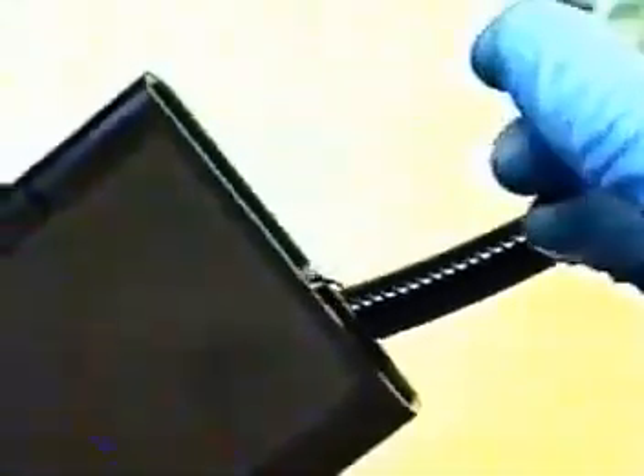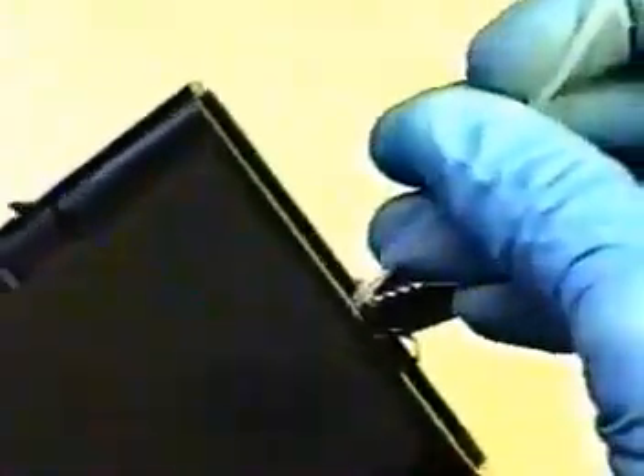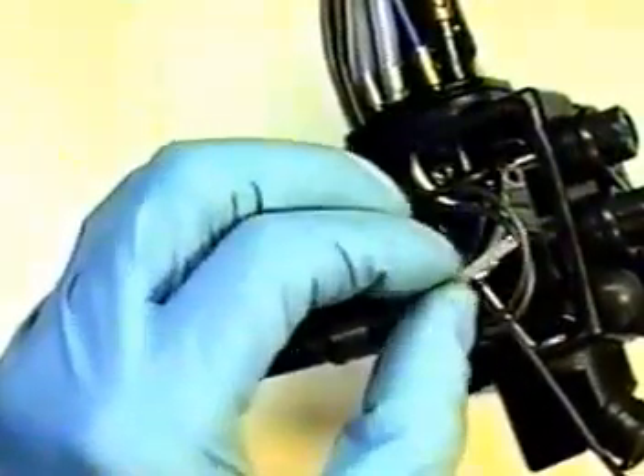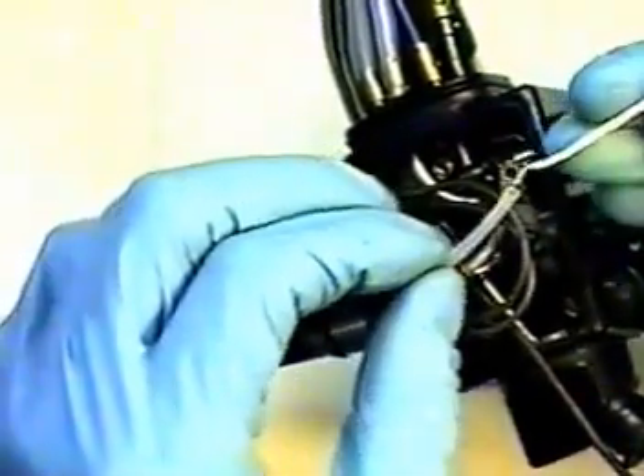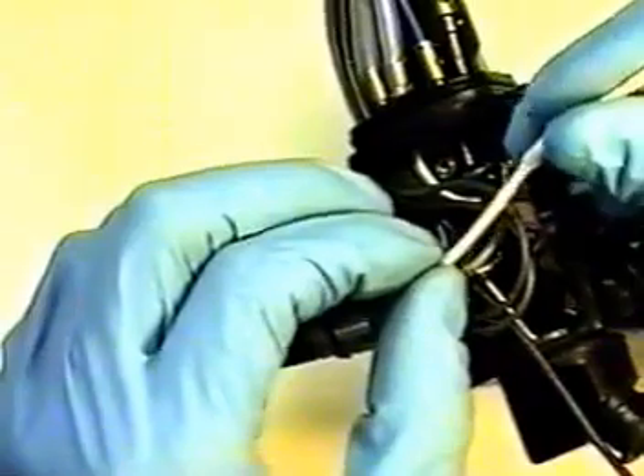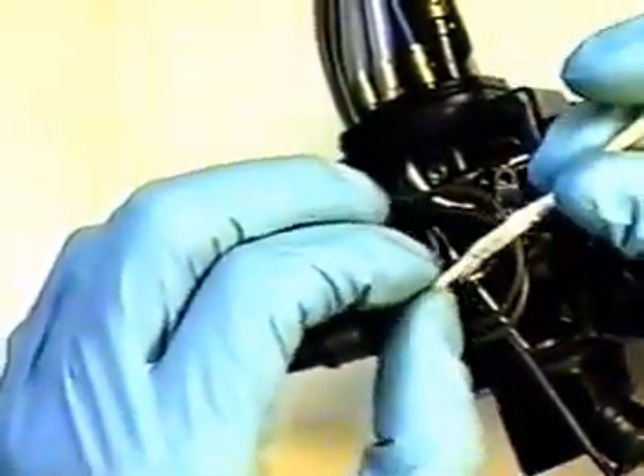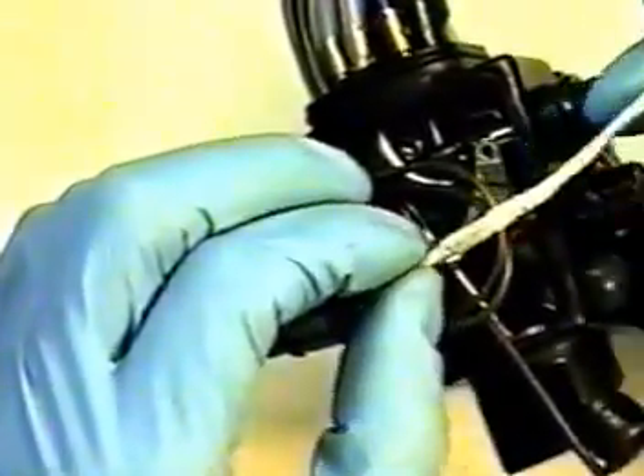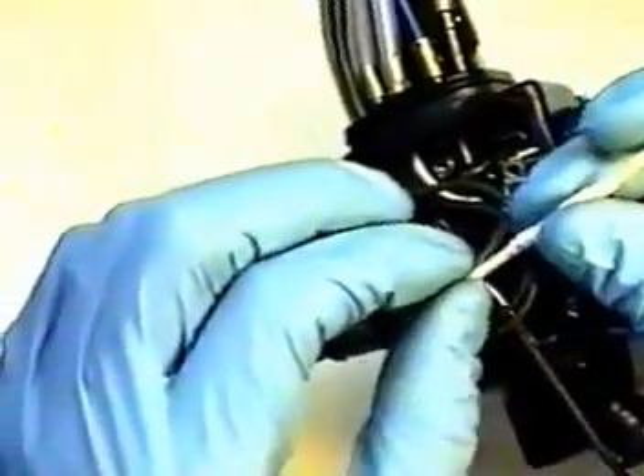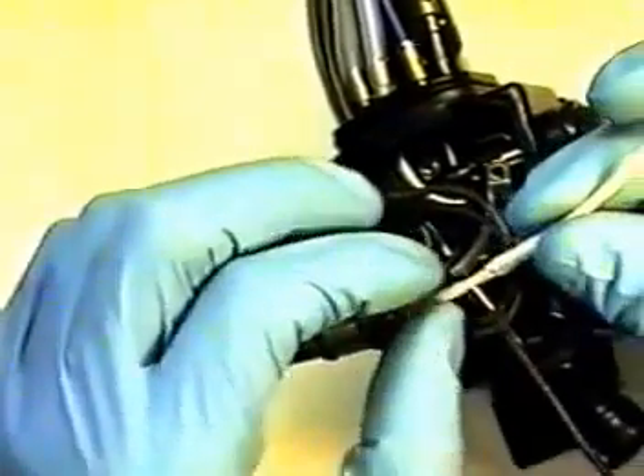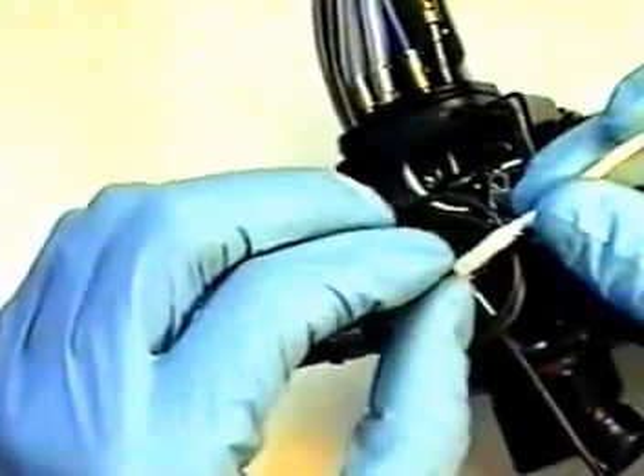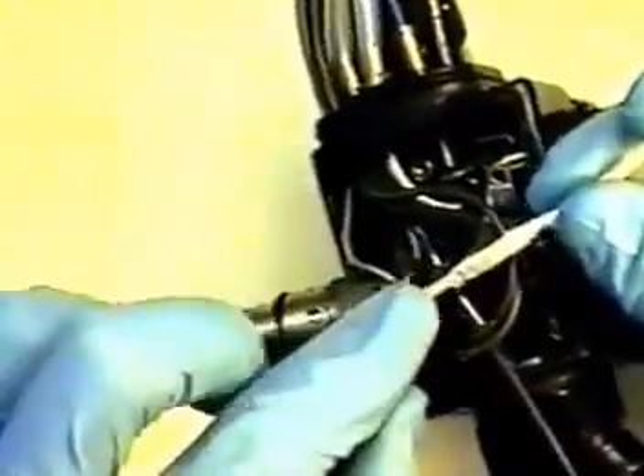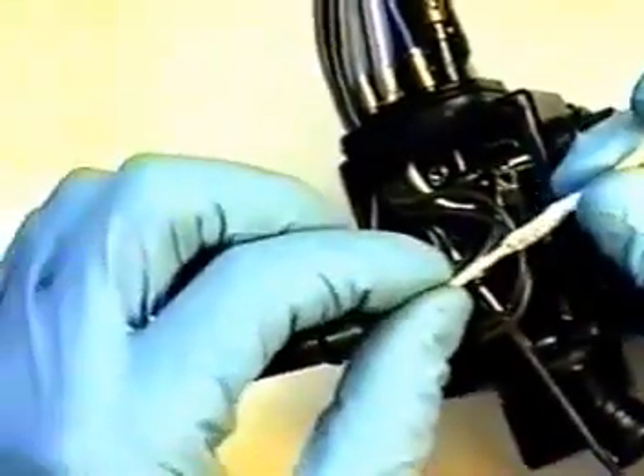Grabbing your video connector, pass a small piece of PVC tubing down through connector, through umbilical cord, so it reaches body control section. We will use this tubing to pull through our CHA CCD wiring harness. Once you're able to pass the tubing through the umbilical light guide portion of the scope, we can now slide in our CHA CCD wiring harness. This will allow us to pull the wire through the entire umbilical control section and out back to the connector. If need be, use a piece of small Scotch tape and tape tightly from tubing to our white tape around CCD wiring harness so it will not pull through and fall off.